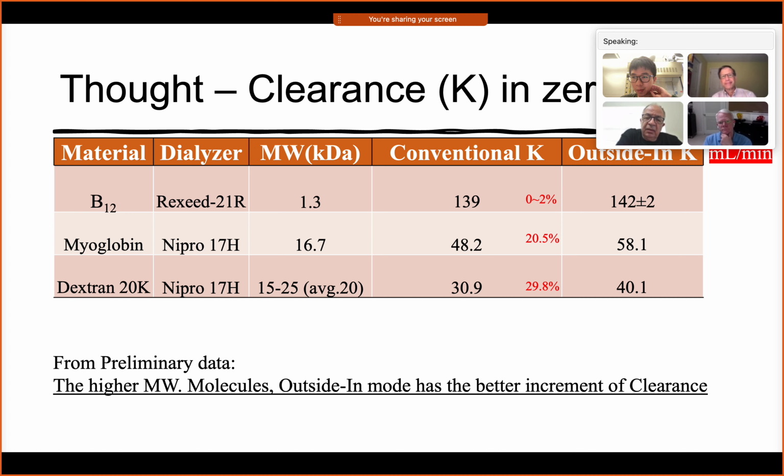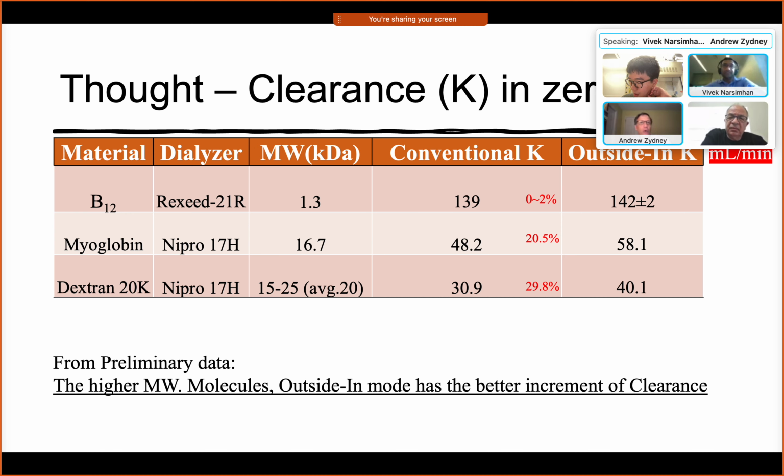Yeah, but I would expect the fouling would be quite different though. You're exactly right. The explanation I gave was in the absence of fouling, and if there is fouling going on, and the fouling characteristics are different depending upon whether you're inside out or outside in, that's an added complication.